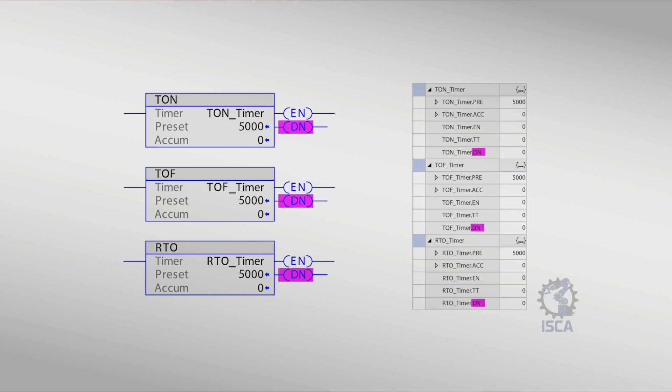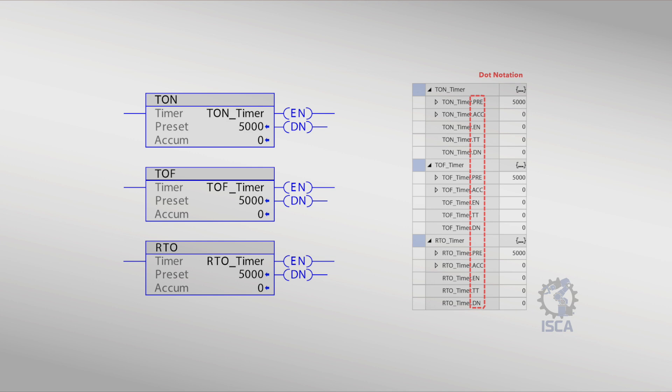Done bit, DN, indicates that the timer is done timing. This is achieved by the accumulated value equaling the preset value. In Studio 5000, you can address these timer elements using dot notation, such as timer.dn to access the done bit.